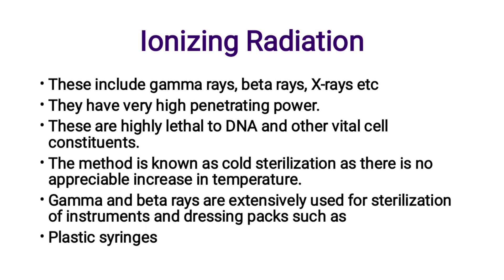Ionizing radiations include gamma rays, beta rays, and X-rays. They have very high penetration power and are highly lethal to DNA and other vital cell constituents. This method is known as cold sterilization because there is no appreciable increase in temperature. Gamma and beta rays are extensively used for sterilization of instruments and dressing packs.